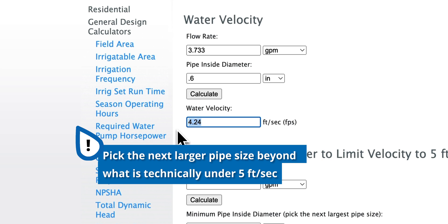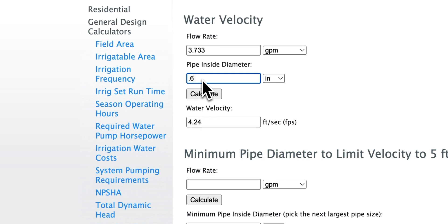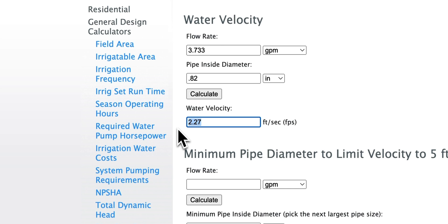So in our case, three quarter inch is a good number to land on. 224 gallons per hour going through three quarter inch tubing has a water velocity of 2.27 feet per second — well within the parameters of the 5 feet per second rule. This illustrates why it's important to check both water velocity and friction loss, as the friction loss in the half inch tubing would be incredibly high. So we're going to follow the rule and go with the next largest pipe size up.